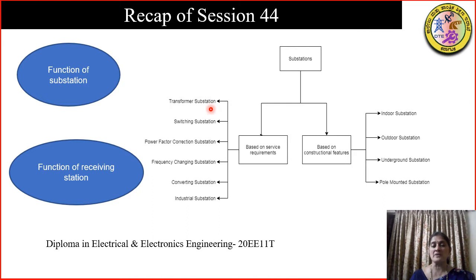Based on service requirement, we had transformer substation, switching substation, power factor correction substation, frequency changing substation, converting substation, and industrial substation. The industrial substation is for individual industrial consumers. The converting substation converts AC to DC. The frequency changing substation changes the frequency. The power factor correction substation works on improvement of power factor. The switching substation is for switching purposes and the transformer substation changes the voltage level.